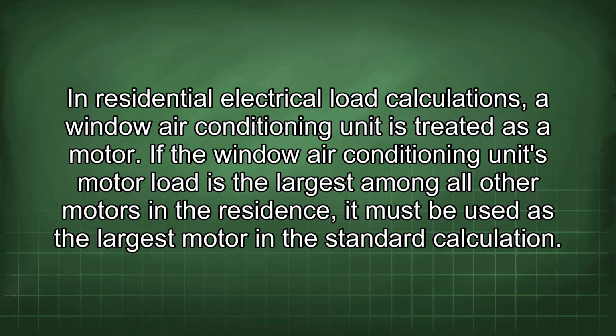In residential electrical load calculations, a window air conditioning unit is treated as a motor. If the window air conditioning unit's motor load is the largest among all other motors in the residence, it must be used as the largest motor in the standard calculation.